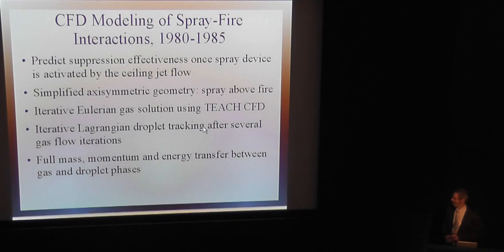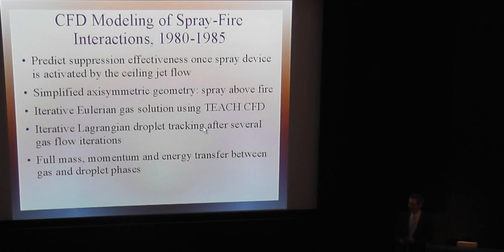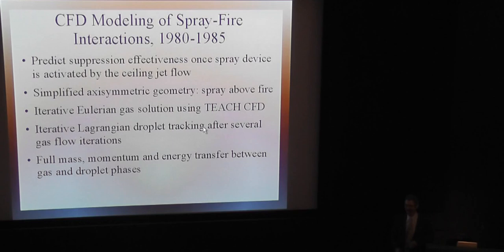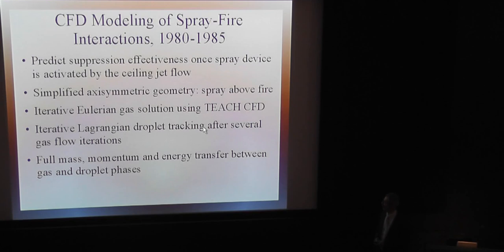That's the re-examination of the ceiling jet formulas. Now that you know the dirty details behind those original formulas, you can forget about them and move on to something new and better. That was the work from the early 1970s. Then in the early 1980s, I wanted to see: now that we know the spray device or detector is activated, what's going to happen to that water? How is it going to get to the fire? Very small droplets might get blown away by the plume and deflected, while very large droplets with strong momentum could get right through the plume and perhaps modify it — it was really interesting to figure out.